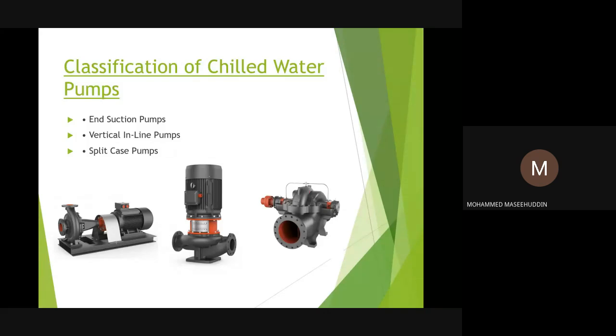Then the third pump, which is used mostly in the secondary chill water circuit, is a horizontal split case pump. Unfortunately, I don't have a blown up picture of this type of pump as of now. It is called horizontal split case because, as the name itself indicates, when you split it in half from between, it has two impellers and two mechanical seals on both sides, and you can take the suction from both sides of the pump. The other side is not visible in the drawing. You can take the suction from both sides of the pump.